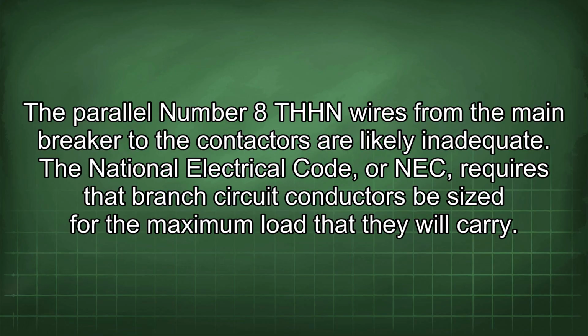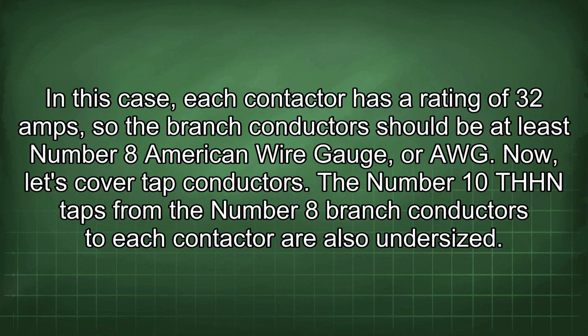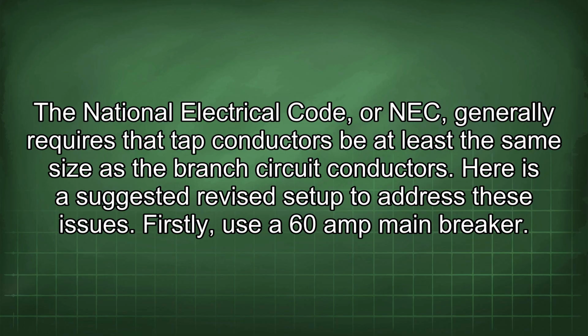The National Electrical Code, or NEC, requires that branch circuit conductors be sized for the maximum load that they will carry. In this case, each contactor has a rating of 32 amps, so the branch conductors should be at least number 8 American wire gauge, or AWG. Now, let's cover tap conductors. The number 10 THHN taps from the number 8 branch conductors to each contactor are also undersized.